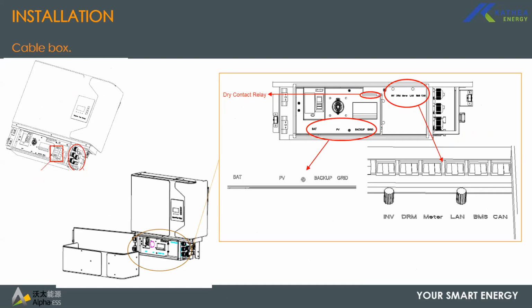So this is basically how the inverter looks like. So this is the inverter. The undercover, which is the small strip cover on the inverter, can be removed to access the cable box. So when you are facing the inverter, your cable connections are on the right for the grid and backup, and the PV. The PV is at the far back, and then the grid cable clamps and the comms cable clamps are at the front.